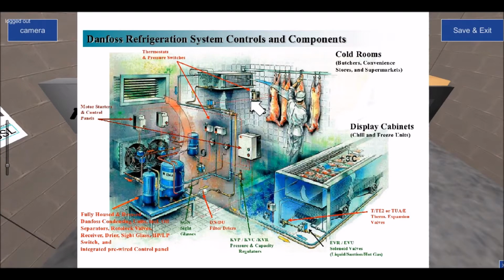It could be anywhere between 2 and 4 degrees, normally in high temperature, so that you don't have short cycling of the compressor. You would have maybe a 4 degree differential. It could be even as high as 6 degrees, but normally it's about 4 degrees differential.